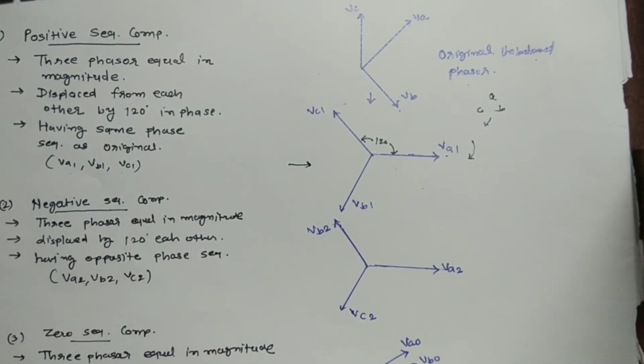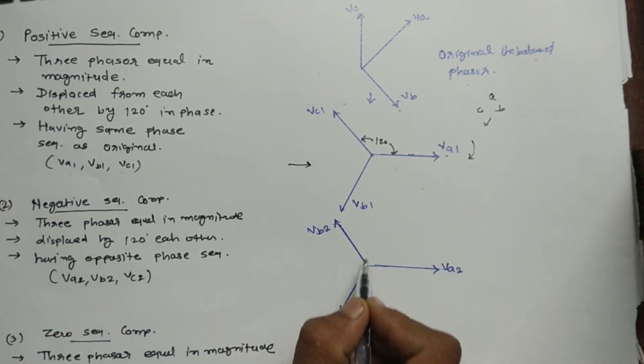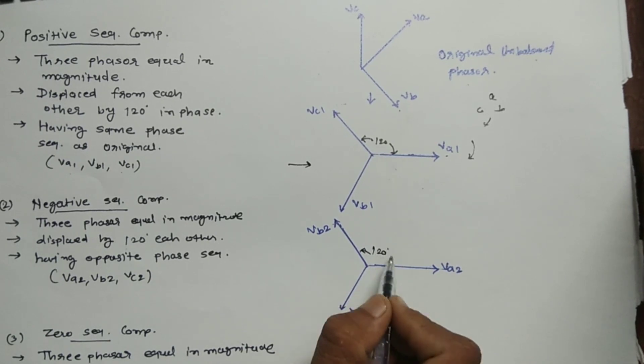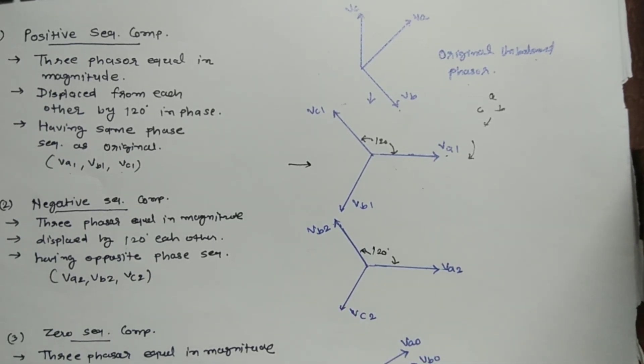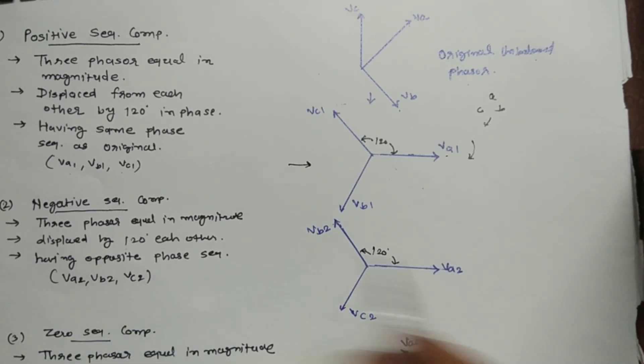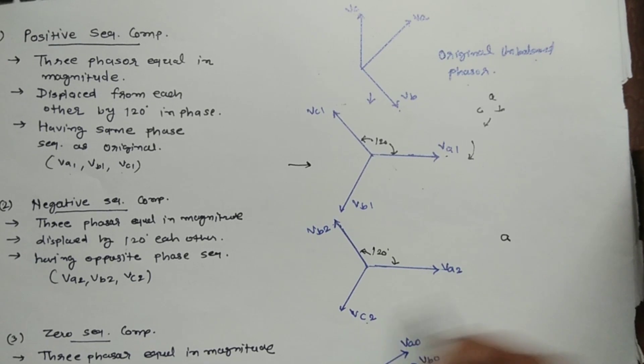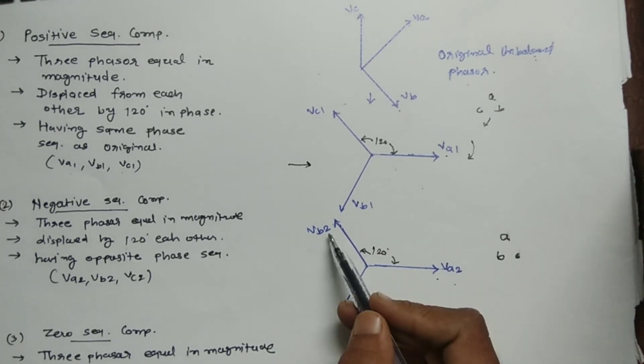Now the negative sequence component. In this component, the three phasors are also equal in magnitude and displaced by 120 degrees from each other. But the difference is the phase sequence — here the phase sequence is A, C, B, which is the opposite of the original unbalanced phasor. It is indicated by VA2, VC2, and VB2. That is the negative sequence component.